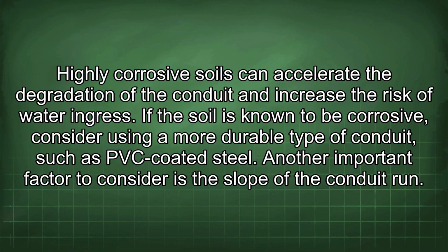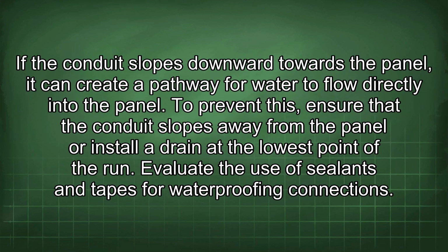Another important factor to consider is the slope of the conduit run. If the conduit slopes downward towards the panel, it can create a pathway for water to flow directly into the panel. To prevent this, ensure that the conduit slopes away from the panel or install a drain at the lowest point of the run. Evaluate the use of sealants and tapes for waterproofing connections.